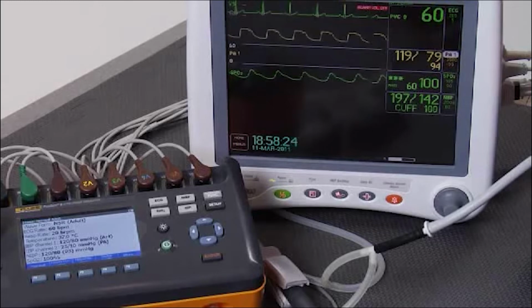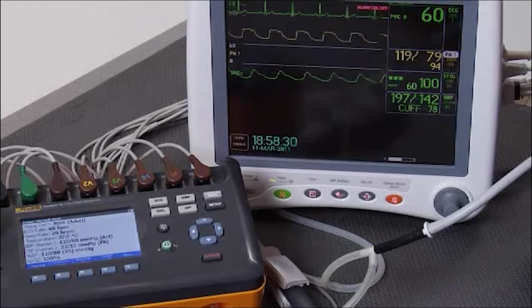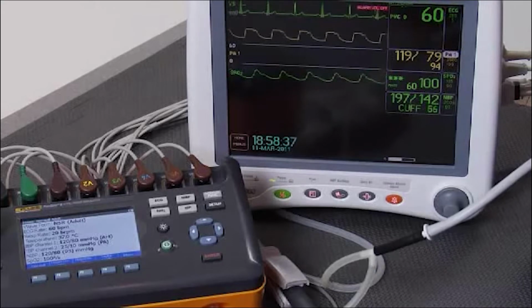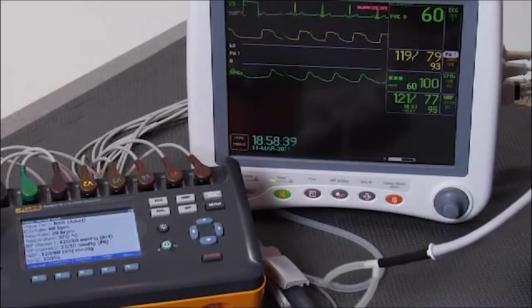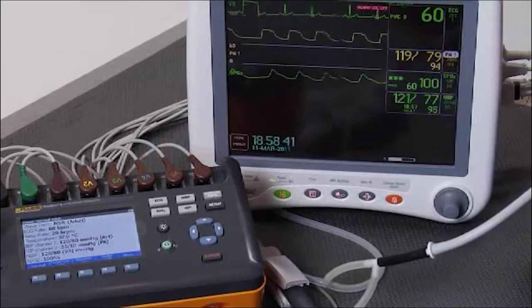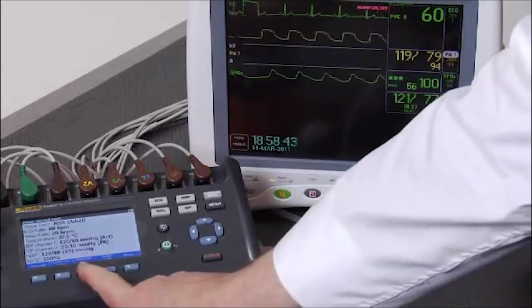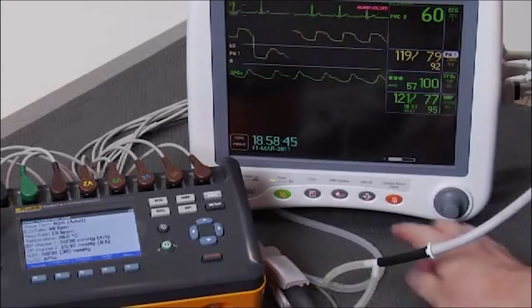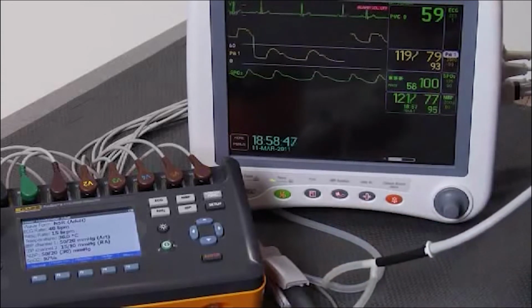And the cuff is making its measurement now for the NIBP reading. O2 sat is 100%. There we go, 121 over 77 versus 120 over 80, pretty good. We'll go to hypotensive now and start another cuff measurement.